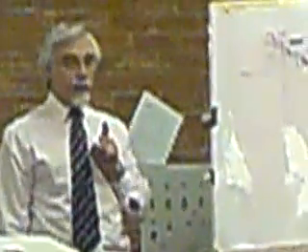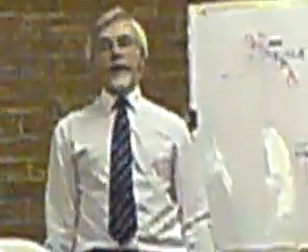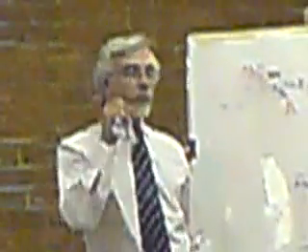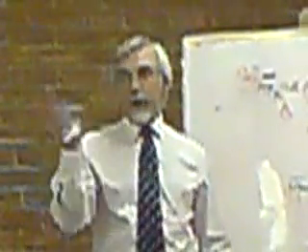Are we going to spike it? Technically, you don't have to spike it because the job's in the box, and what we're doing is we can expose the cable to the point where we're going to spike it. But it's iffy ground. Are you with me? What they say in the regs, if you can identify the cable with certainty, you don't need to spike it. You understand?